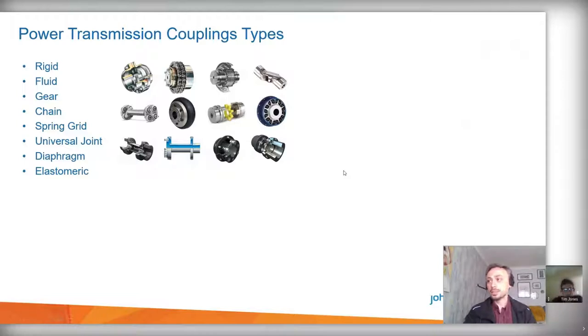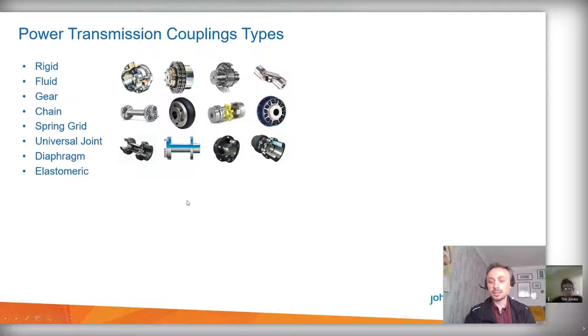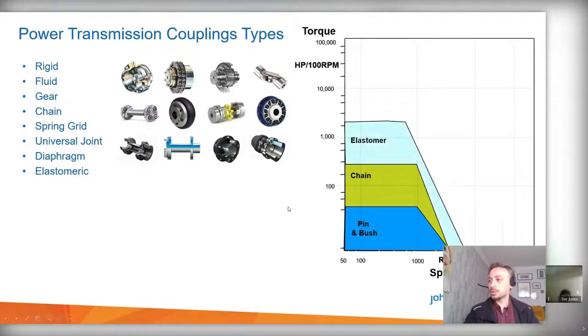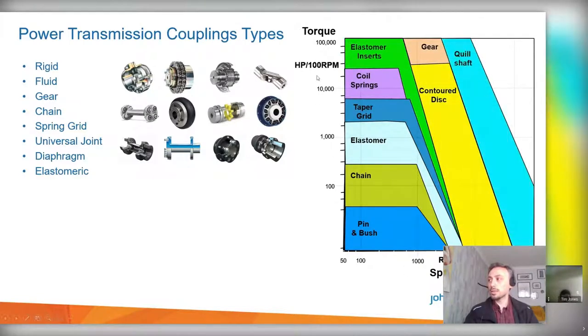There are various coupling types in industry: gear couplings, grid couplings, spring grids, universal joints, diaphragm couplings, solid disk diaphragm couplings, damping couplings, and fluid couplings. All have different purposes. You need to understand your operation, what catastrophic events may occur, and select accordingly. The main selection criteria are torque and speed requirements, and different coupling types meet different market requirements. Flexible membrane couplings can be designed for virtually any speed, torque, or misalignment requirement, though the combination of all three defines product complexity and cost.